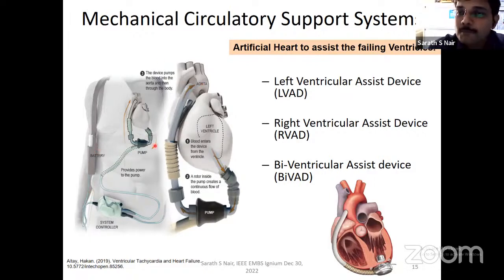But how do you rotate the pump? How do you give power to the pump? This pump needs to be operated by electrical energy. So for that, a cable is required. The cable comes out of the human body through a small puncture or a small hole in the skin, and then the cable gets connected to a controller. The controller will have sufficient memory, sufficient control systems, and all the electronics required for monitoring and controlling the pump activity, as well as the battery. So this battery may be sufficient to operate for 24 hours, 365 days, as long as the device works, as long as the patient can support it.